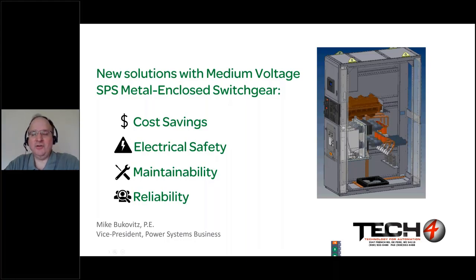Michael McClellan asked me to give a presentation that we titled New Solutions with Medium Voltage Switchgear. The focus is in 4 areas. The first is savings, both cost savings as well as space savings, and space savings frequently equate to cost savings if you're building a new electrical room as well. Second, improvements in electrical safety in metal enclosed switchgear. We do that primarily through insulated bus to mitigate shock hazards, and arc flash mitigation through active arc quenching and arc flash relays to mitigate arc flash risk.